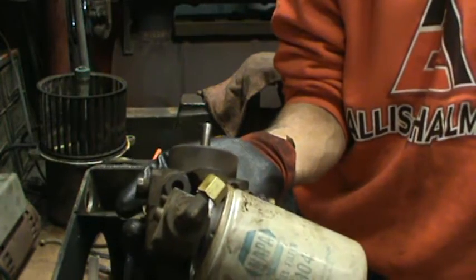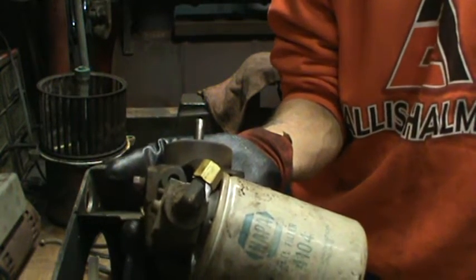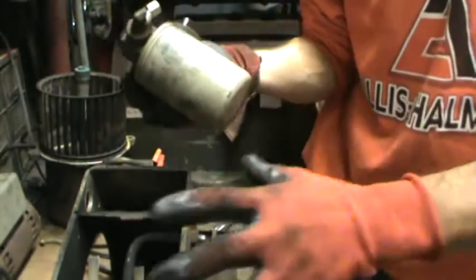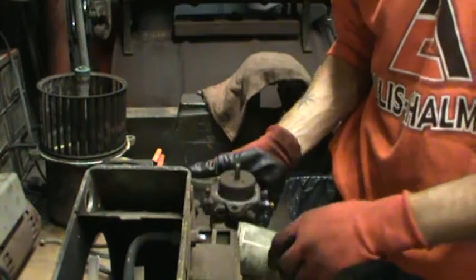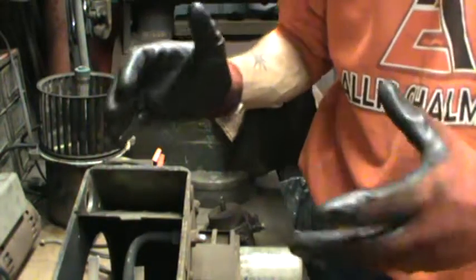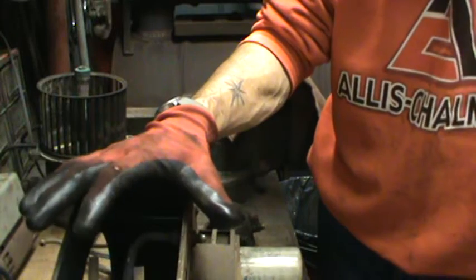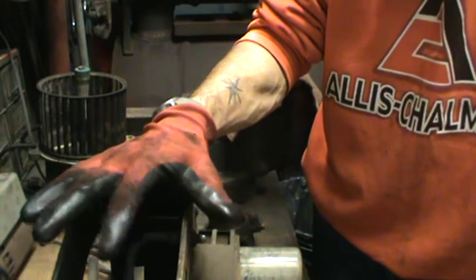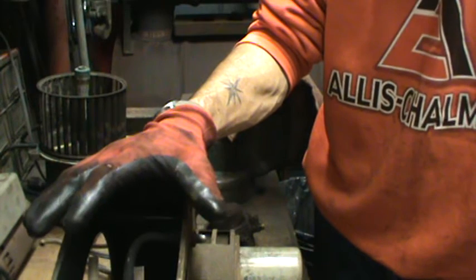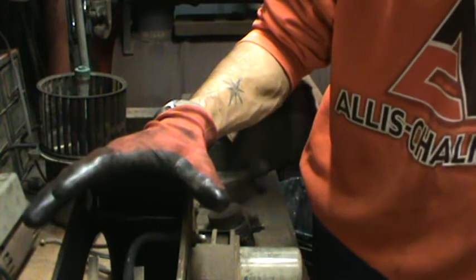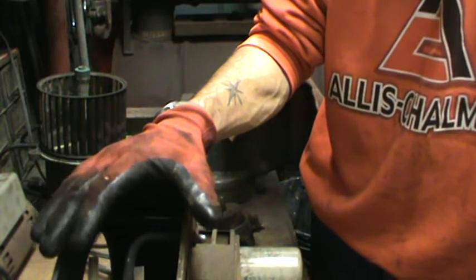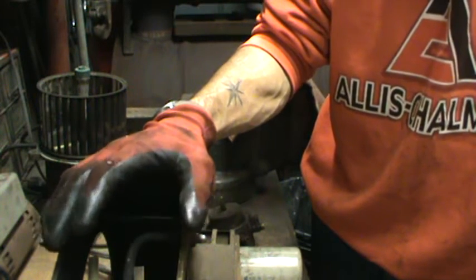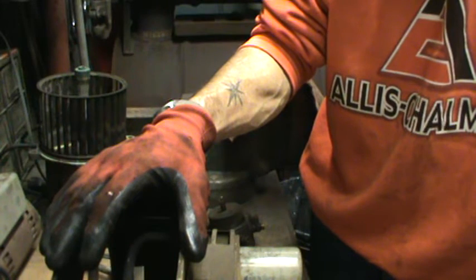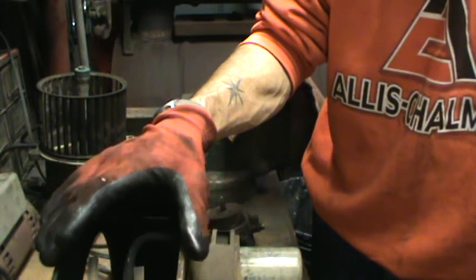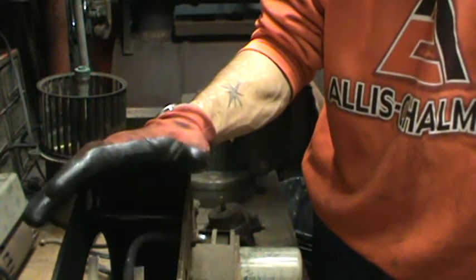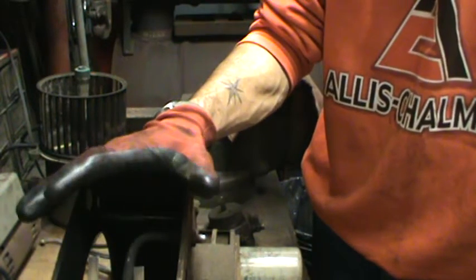I have seen oil furnace technicians change the jets around to get them to run more efficiently, use less fuel and burn more efficiently. I've seen them switch out the nozzles, not necessarily the angles, but the gallons per hour on the nozzles, and each of them has their own specific pressure.